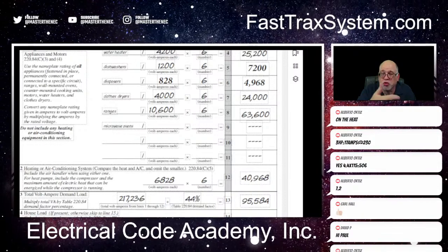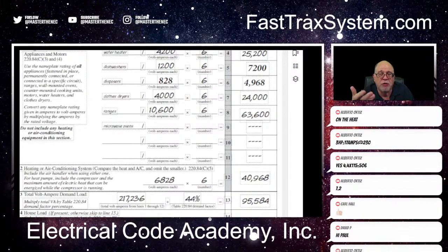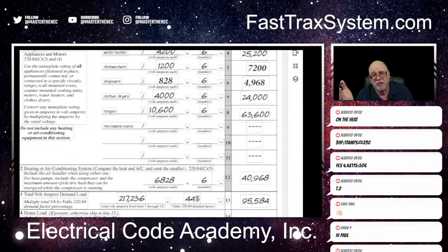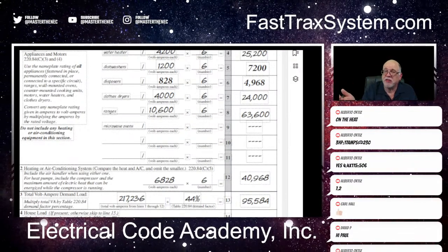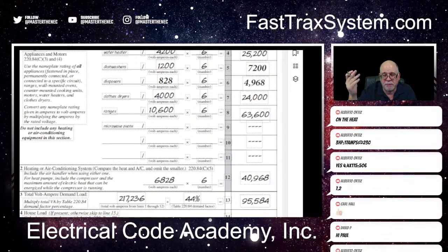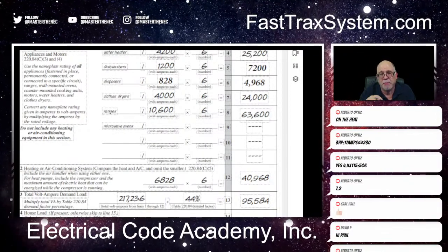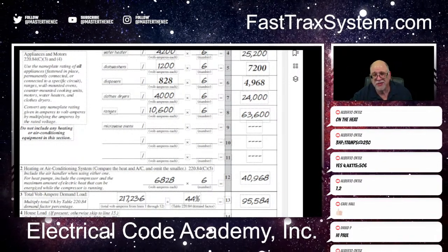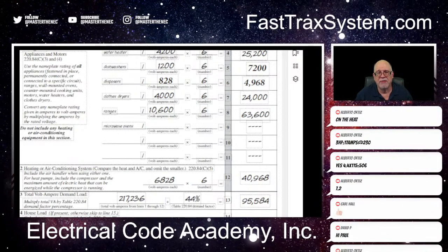That's what the neutral contribution actually is. You don't round that up for the neutral. So you just submit 14.58. Makes sense? Now, other applications, hot conductors, service, go ahead and do the rounding: 0.5 or greater, round up, okay? 0.4 or less, round off, okay?